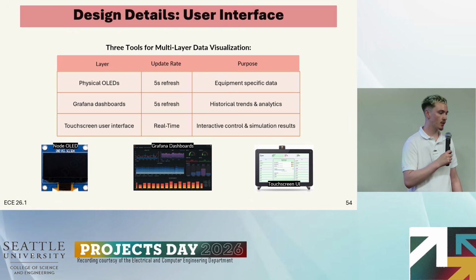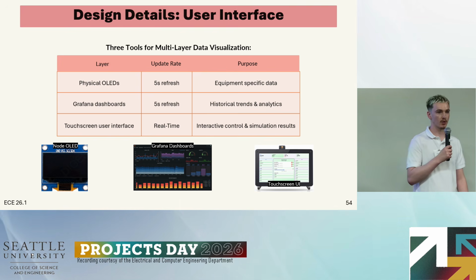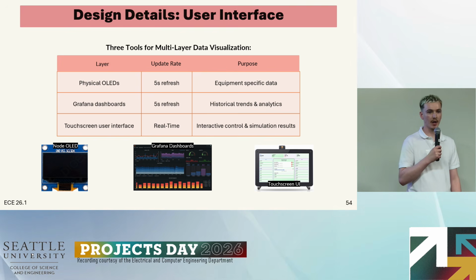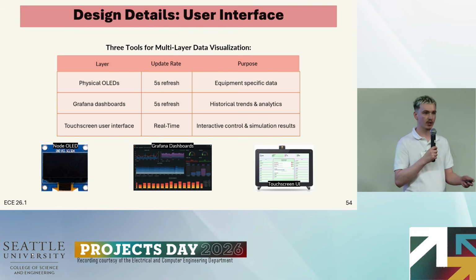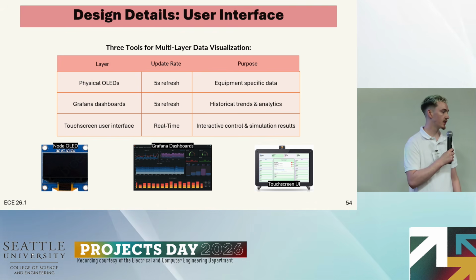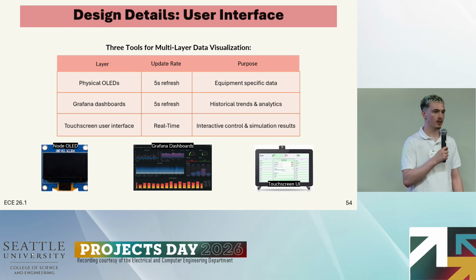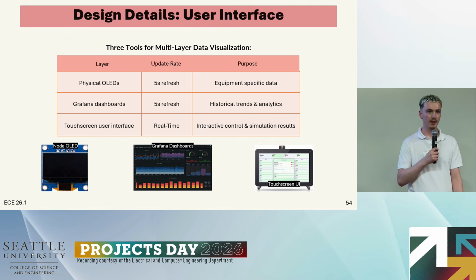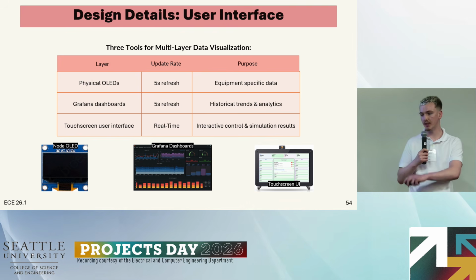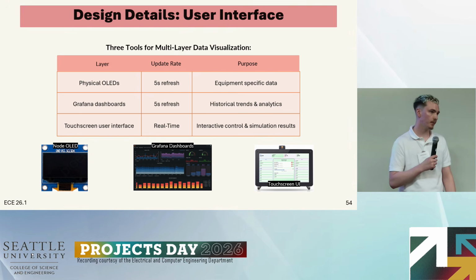We also have 2 on our touchscreen interface. The first is a Grafana dashboard. This will show historical data. For example, if there's a power outage event, it'll show you how the system changes over time during that event. And finally, the touchscreen user interface. This allows the user to input some values, such as changing the number of fans or other things that you can't do by just placing modules in and out.